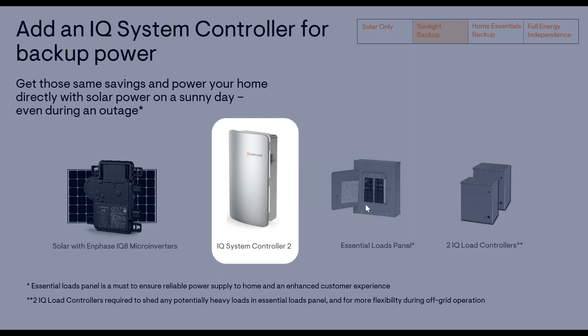I hear people calling it a smart switch as well, but it's an MID, and it's going to allow you to isolate the PV, the loads in the house, and batteries, if there are any on the system, and form a microgrid so none of the energy generated or being utilized will ever flow to the utility, which would be against code.